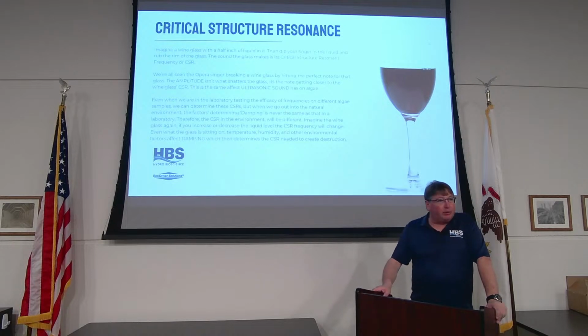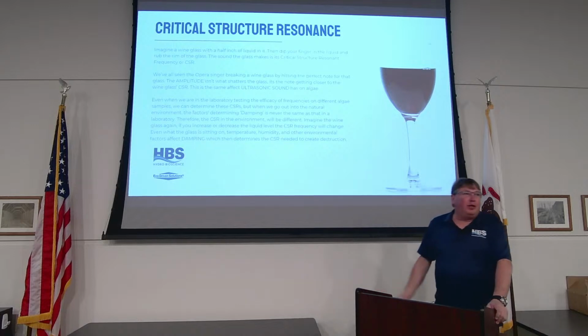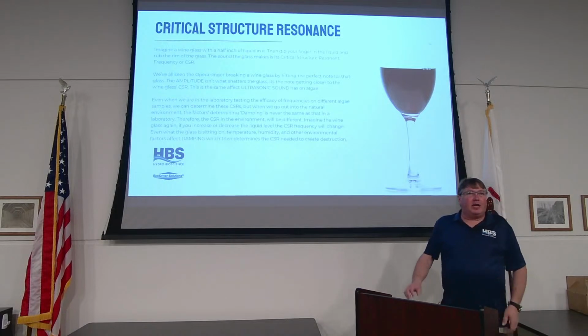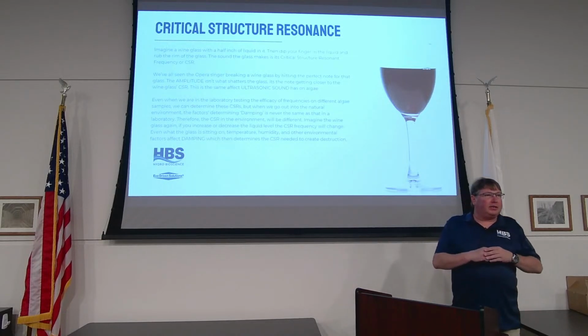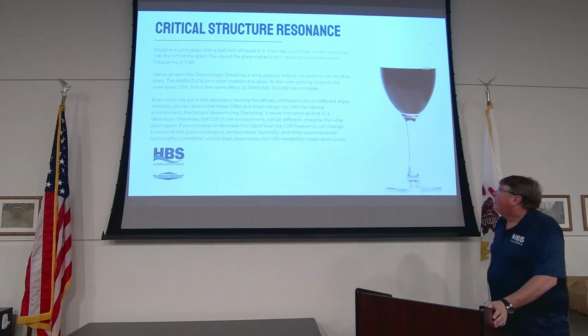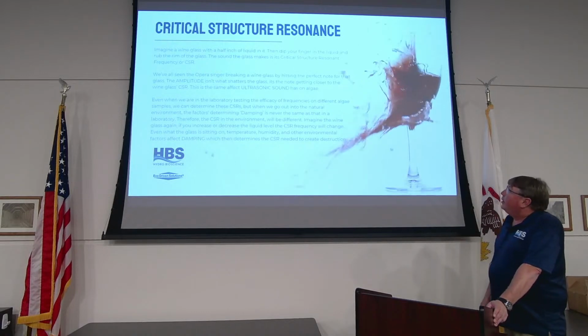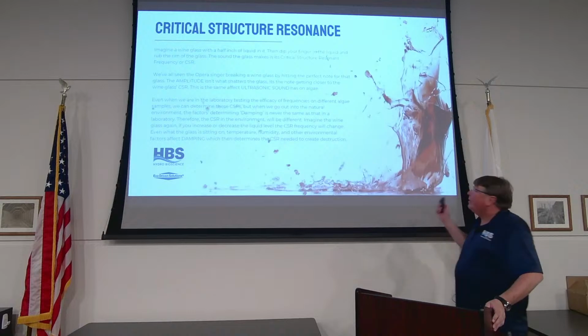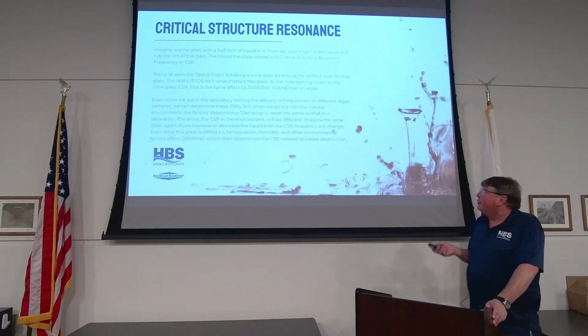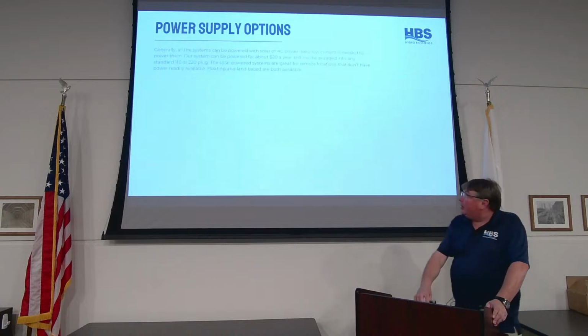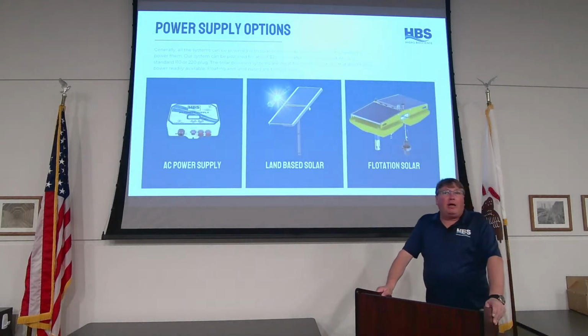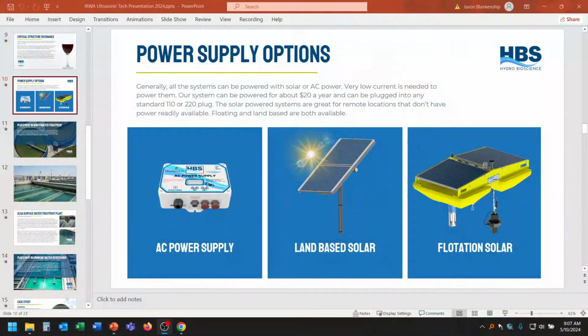If there was just one frequency for algae, I'd be more than happy to put it in there and just run it, but there's not. It's all dependent on distance, your TSS, the temperature of the water. All these things come into play when you're talking about a critical resonant frequency here. So there it goes. When you hit that frequency, that's what happens. Same thing with algae. It happens with everything. So when you talk about the critical resonant frequency doing this, the damping is a big factor. It's a very big factor.